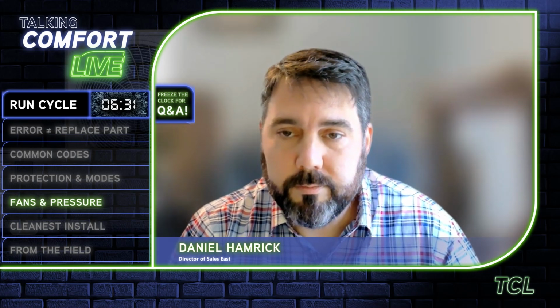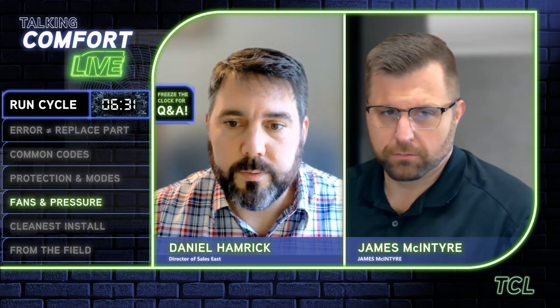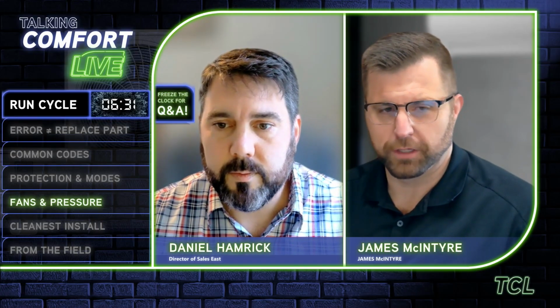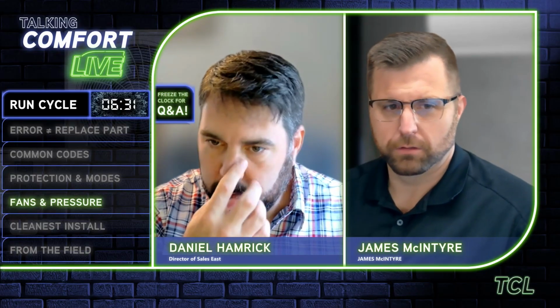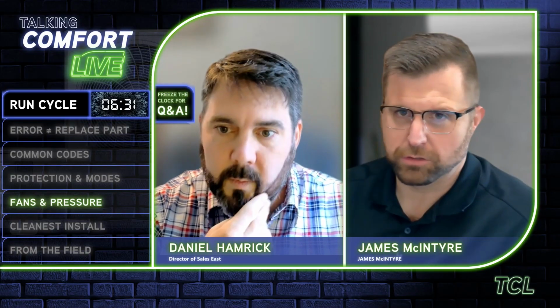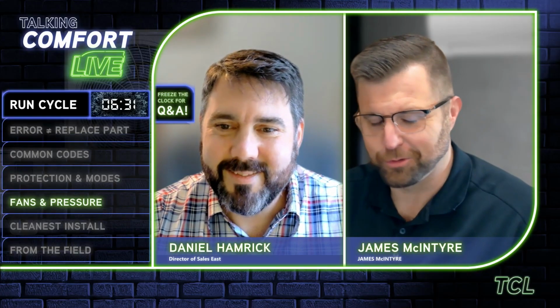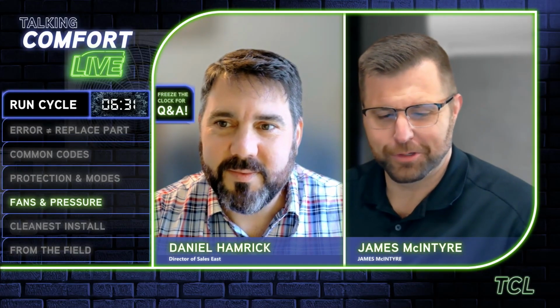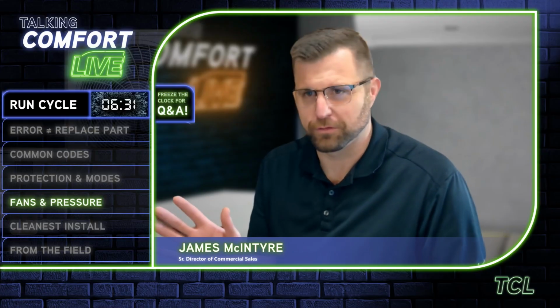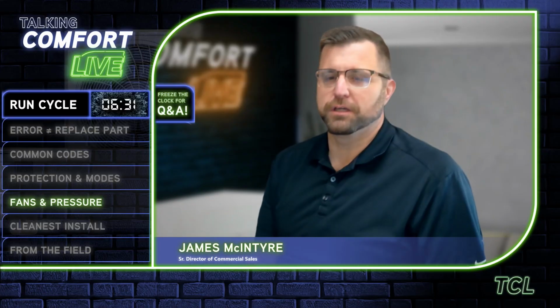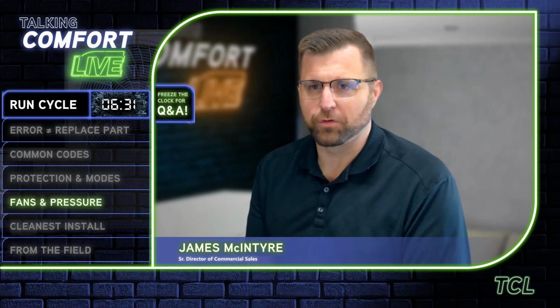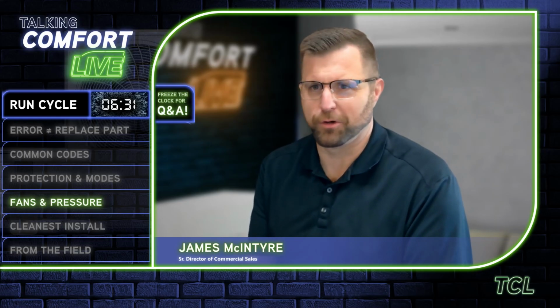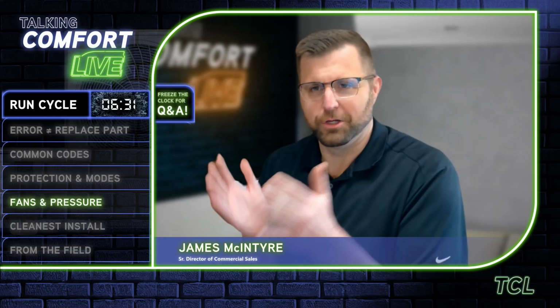Yeah. Normally when somebody calls in tech support on that, unfortunately, we end up, not you guys that are watching, it's your competition, it's not you guys, spending an inordinate amount of time talking about, I know it's not swapped, I know that. But it's like, okay, let's just go through it for the sake of it. If you had a stuck EEV, it's going to help you identify that, for example. You're feeding refrigerant to one that you don't want to feed to. So you've got two of them that operate normally, but a third one doesn't. Now I've got one that we're focused on.